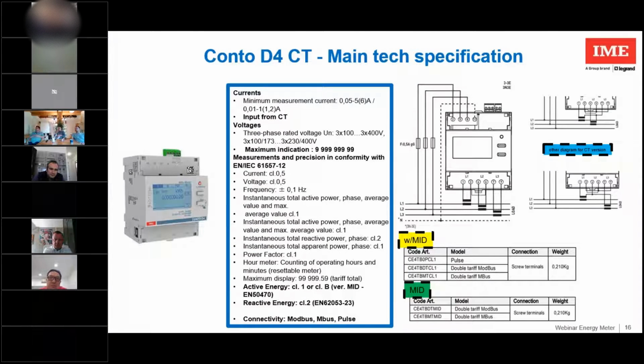This is the Conto D4 with the current transformer insertion. Also here we have the maximum indication in 9 digits. The number of decimal places in the energy value depends on the current transformer. So if you have a higher current transformer ratio, your maximum indication changes in the decimal part shown on the display for the energy. For the other instruments, the Conto D4 63 and the Conto D2, you have 2 decimal points and 7 for the unit part. Also here in the upper part you find the connector for the Modbus and M-Bus protocol, input or output, like the others of the series.